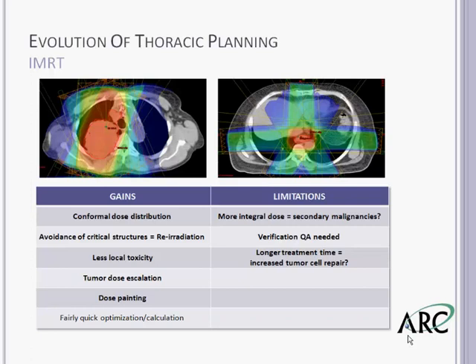However, the benefits of IMRT do come at a cost. First, it's more complex, requiring verification QA. Second, there's the possibility of increased integral dose, where a larger volume of normal tissue receives a low dose of radiation — raising concerns about secondary malignancy. Third, there can be a substantial amount of time to send information to the treatment machine, rotate the gantry, set the field, and verify it, which has led to concerns about tumor cell repair during treatment delivery.